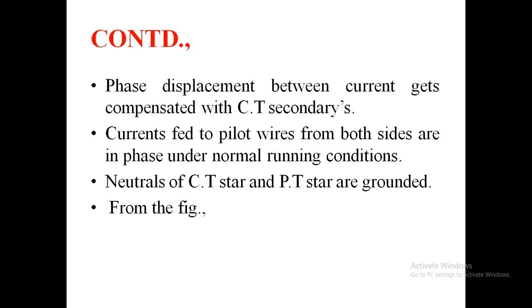So here this circuit is representing the neutral of current transformer and potential transformer stars are grounded. Many transformers have tap changing arrangements, due to which there is a possibility of flow of differential current. For this, the turns ratio of the current transformers on both sides of the power transformer is provided with taps for adjustment.